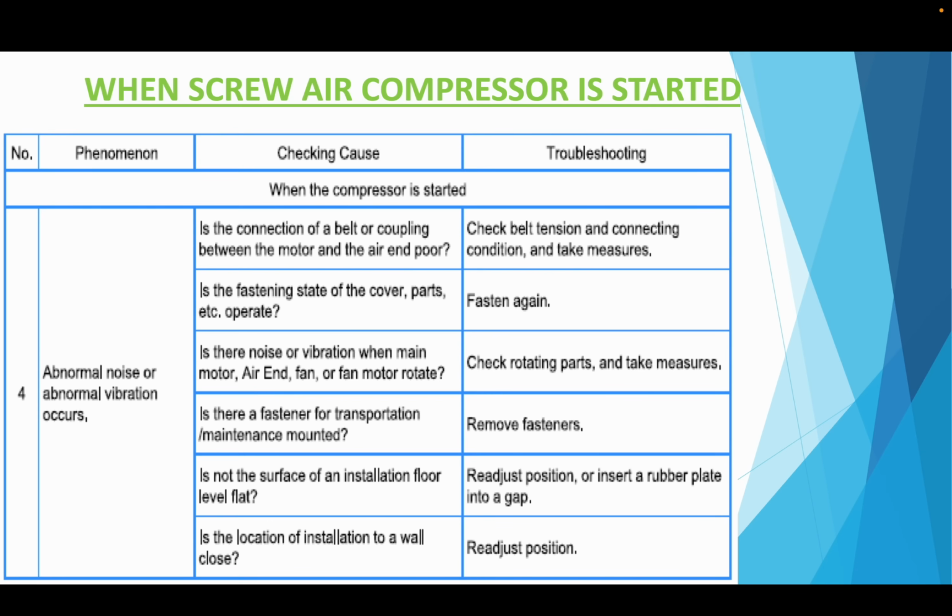If abnormal noise and vibration are coming, then there might be a problem with the belt or coupling. There might be a problem with the foundation fastening nut. There might be a problem with fan motor damage or the bearing getting damaged. Or check if there is any damage during transportation, or check for any installation having unwanted vibration, or loosening up.